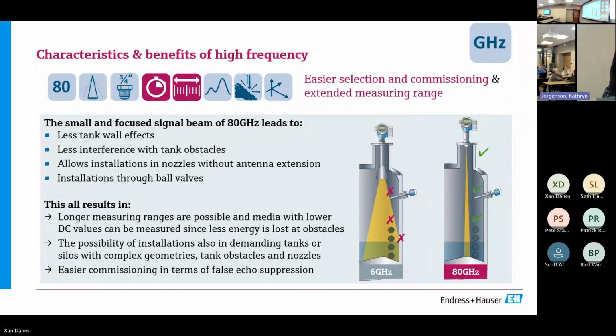I appreciate that. So when we do, for instance, liquefied natural gas, I know that we hit a critical distance because the dielectric's low. For liquefied natural gas, we can use these devices as a high level alarm or high level interlock, but we wouldn't necessarily use them in a 120-foot tall LNG tank.